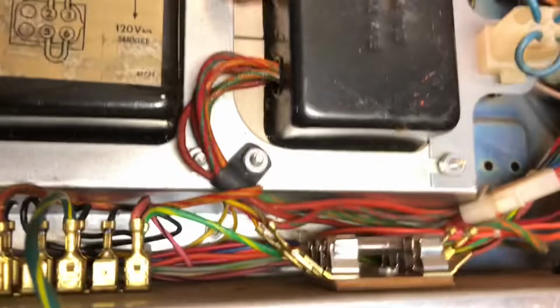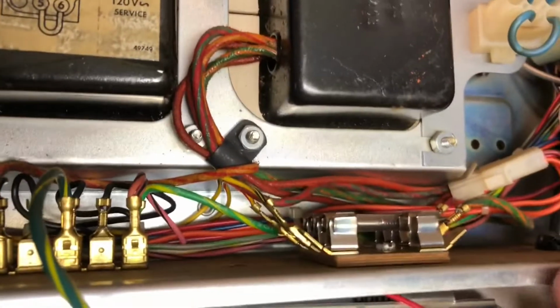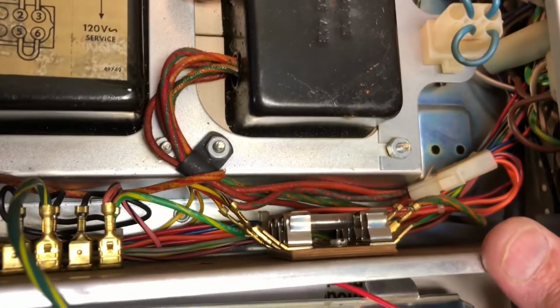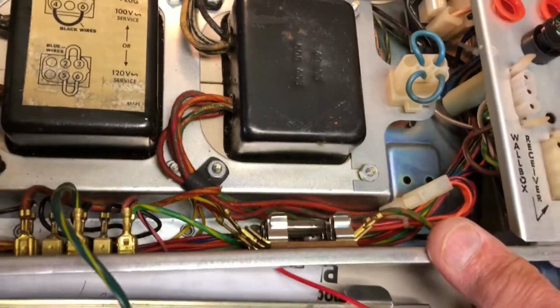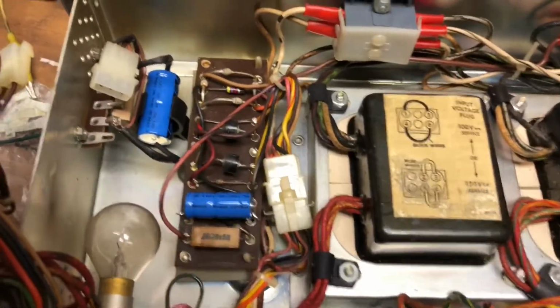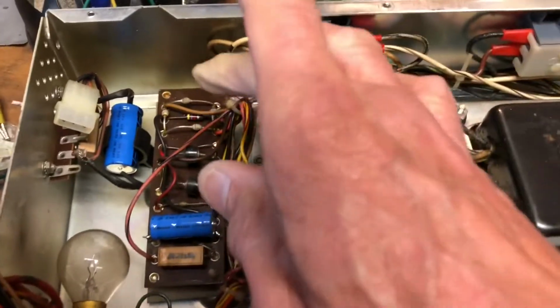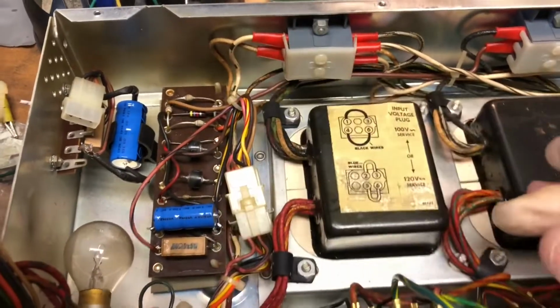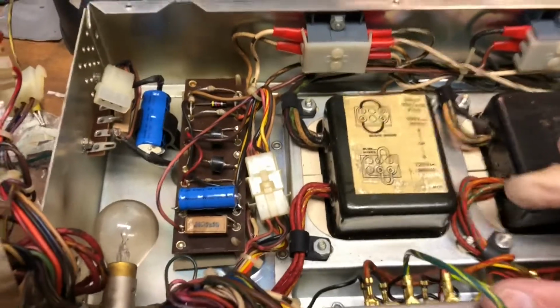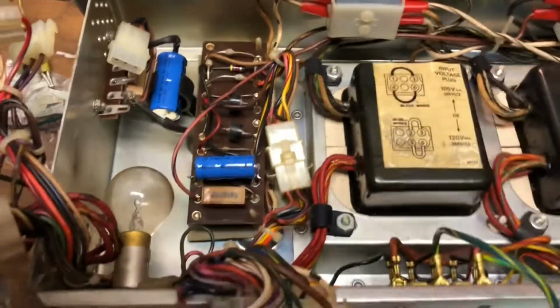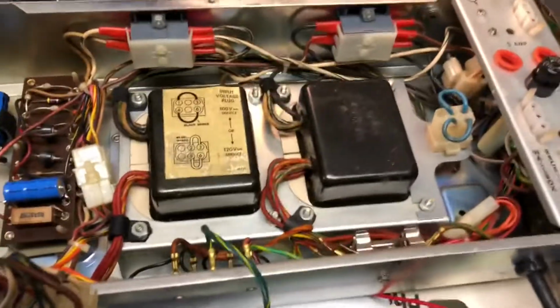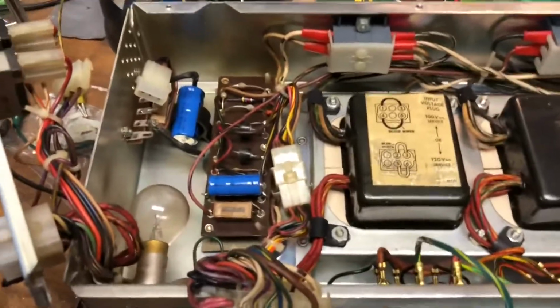Again, there's a host of fuses inside here I want you to be aware of. If they're blown, then you've got to determine why, because that could be a diode over here that went bad, and you'd have to check the continuity of the diodes with the diode checker. I don't think you have to do that. If everything looks good and no fuses are blown, you're probably okay by just checking the circuit breakers and replacing those 3 capacitors.